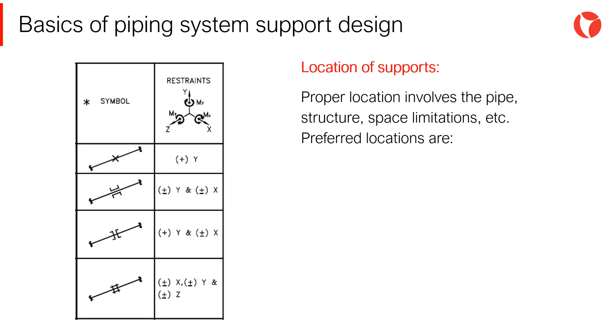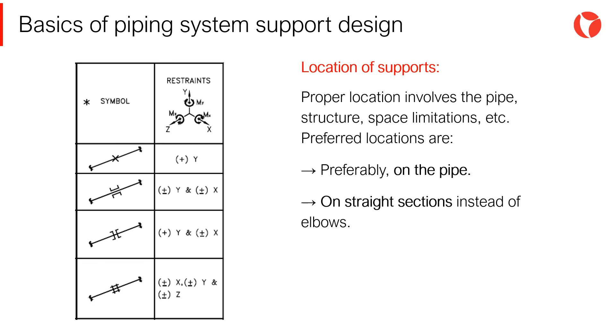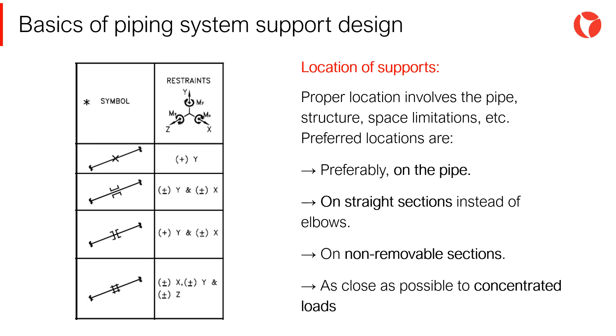The proper location of hangers or fixed supports involves considerations of the pipe itself, the structure to which the load is transmitted, and space limitations. The preferred points for the location of supports are on the pipe itself and not on components, on straight sections of pipes instead of on elbows, on sections of pipes that do not require frequent removal for cleaning or maintenance, and as close as possible to large load concentrations.